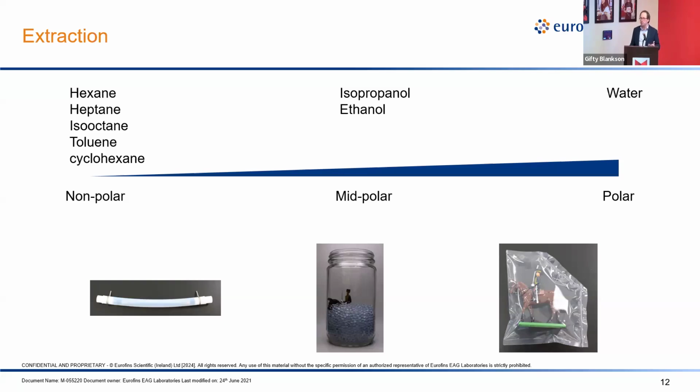And it's like, okay, that makes sense. But then think about it. If I challenged any of you, go out and buy something that's cleaner than a medical device that's built for implant. It's like, oh man, that's rough, right? This is not a Home Depot problem, right? This is a little bit trickier. So a surprising amount of thought goes into this part. We do little studies to see what materials are okay and what kind of problems they could create. Now, if we do see something, we can still address it, but it's not as good as just making sure it never showed up there in the first place.